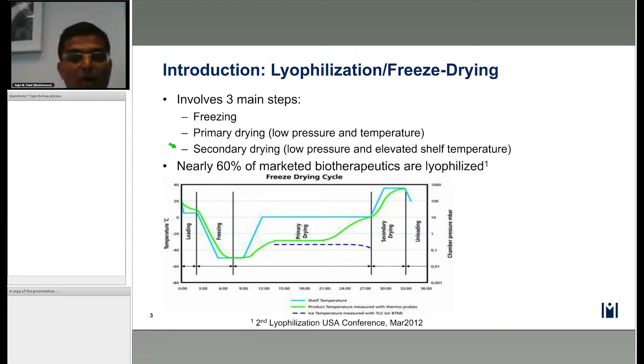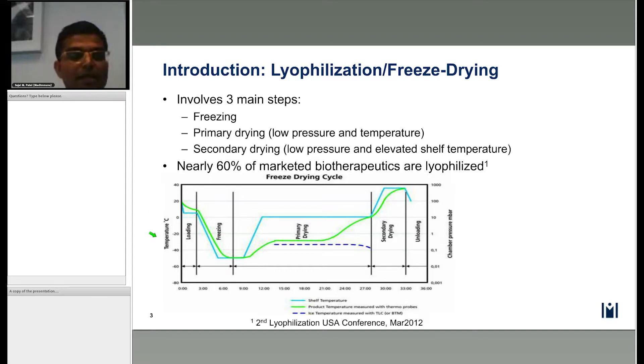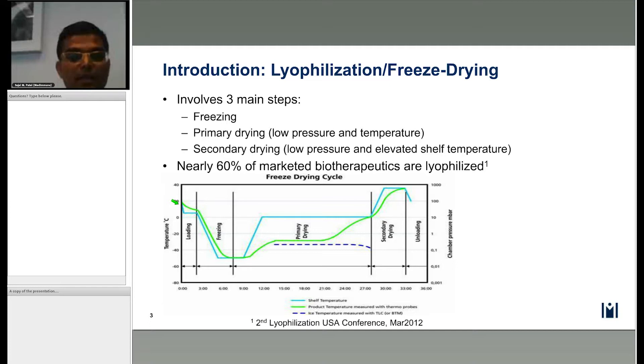What you see in the schematic here is a typical lyophilization process parameter chart. On the left-hand y-axis we have temperature, on the right-hand y-axis we have pressure, and on the x-axis we have time. The process starts with the loading of filled containers — whether vials, cartridges, or syringes — then proceeds through freezing, followed by primary drying and secondary drying, and ends with the unloading of the containers from the lyophilizer.